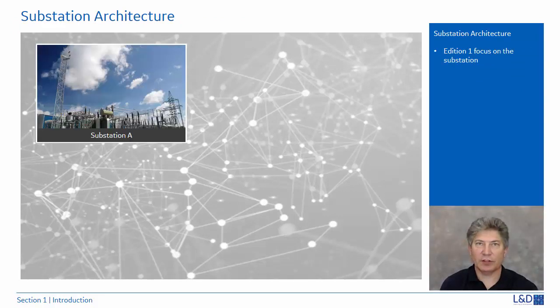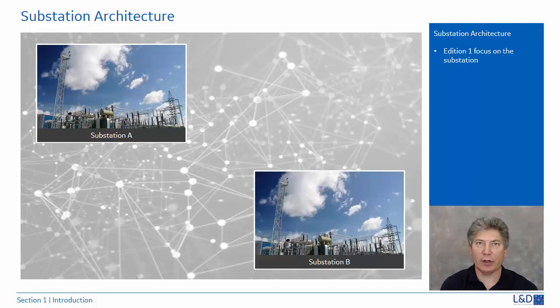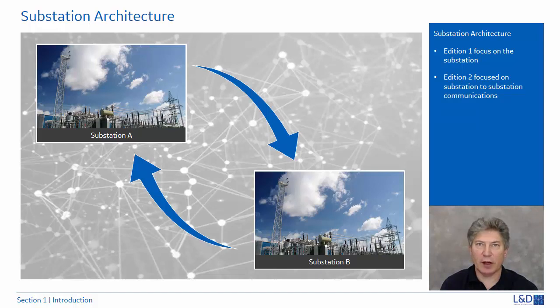In addition to Edition 1 of the standard, the focus was based on substation communication using a local area network and standard GOOSE messaging. In edition two of the standard, the focus is based on substation to substation communications, going beyond the safe confines of the substation and communications, utilizing the wide area network and securing the data within a new type of GOOSE called the routable GOOSE.